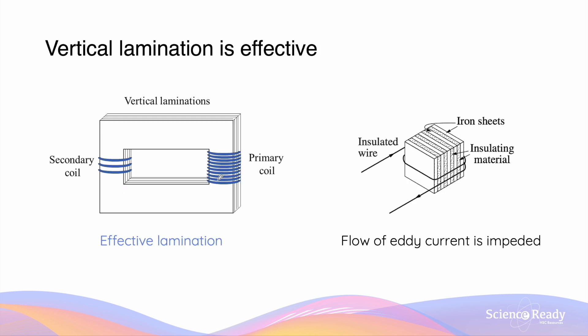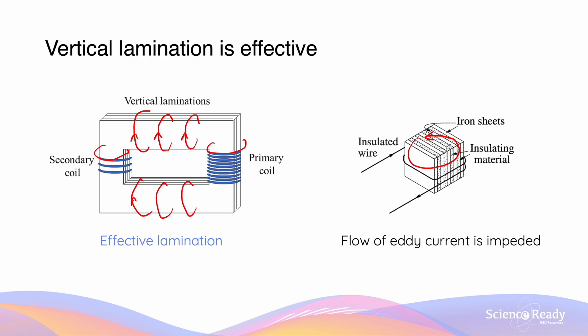It is important to understand that lamination involves cutting the iron core in a very specific orientation, called vertical lamination. The eddy currents induced in the iron core flow in a circular direction — on the top and bottom they flow one way, and on the left and right where the primary and secondary coils are, they flow another way. By cutting the iron core into vertical slices, the eddy current can no longer flow in its original path and must instead flow inside each thin slice, which greatly reduces the total magnitude of the eddy current and minimizes power loss.